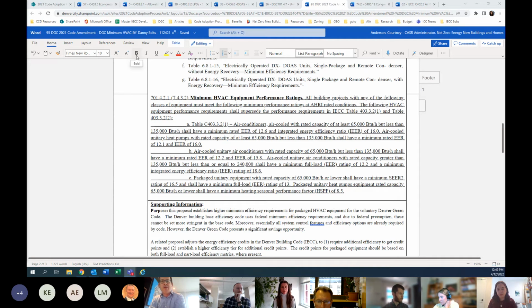The first one is air conditioners, typically packaged but air-cooled, which would have a higher minimum rated EER of 12.6 and an IEER, which is integrated energy efficiency ratio. For those more familiar with residential equipment, it's kind of analogous to the SEER rating for smaller equipment. This would require a higher rating for this equipment. So the IEER, which is an annualized type rating, is really more of a measure of how well the equipment performs over the year, rather than at a specific design condition.